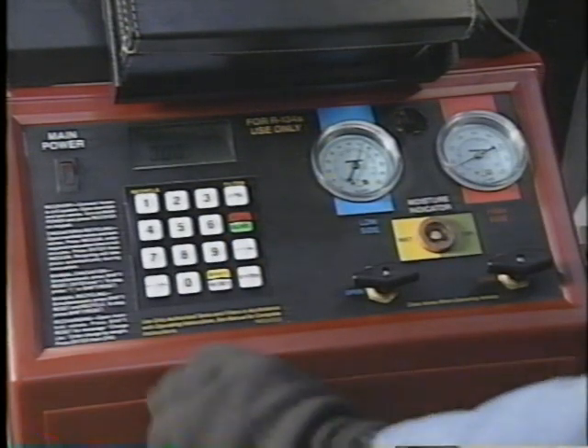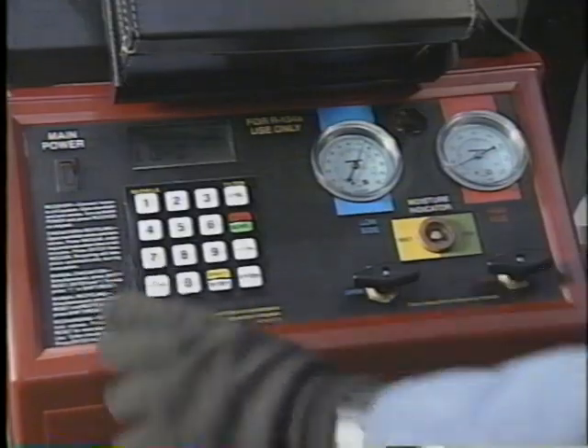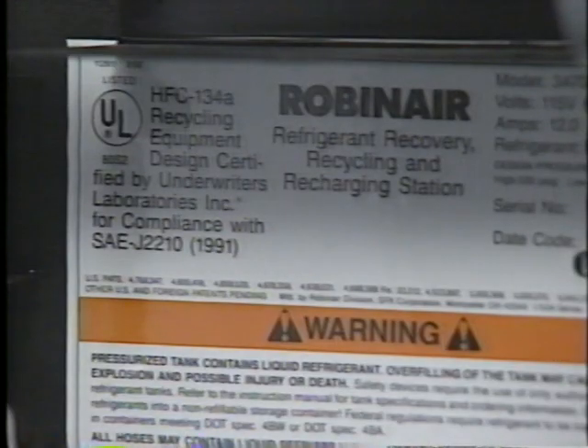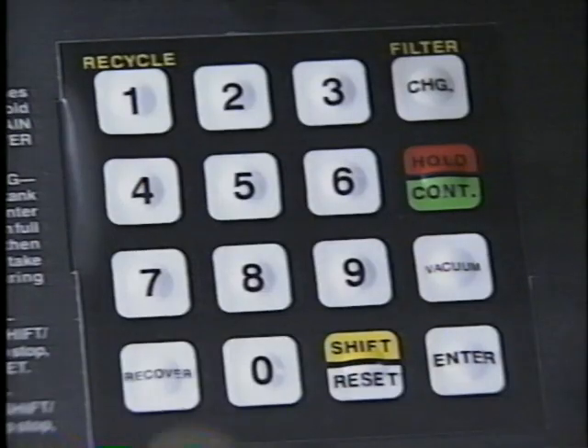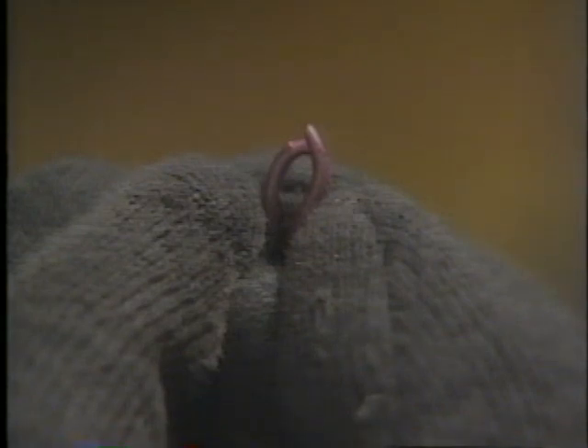An R12 recovery station cannot be used to recover R134A. R134A could damage an R12 recovery machine. Remember, use only a UL-approved R134A machine. Follow the manufacturer's instructions for discharging the system. The cause of the leak was a torn O-ring, which the technician replaces.